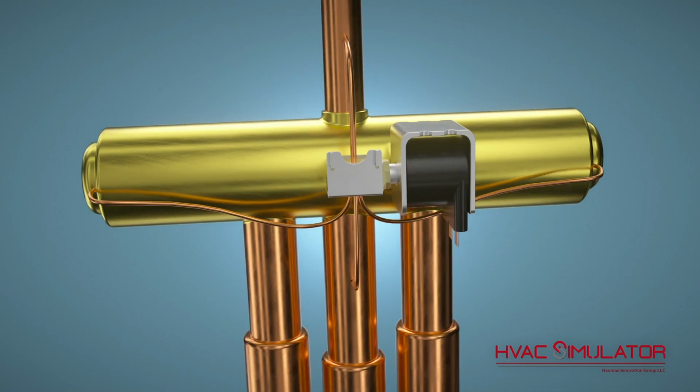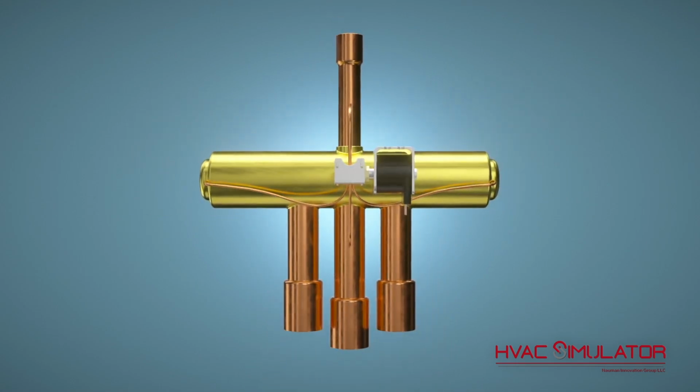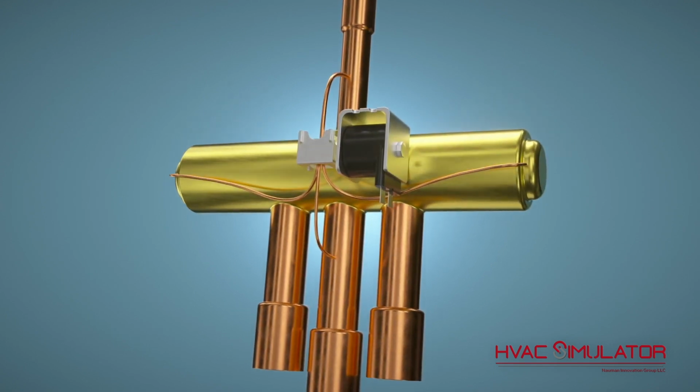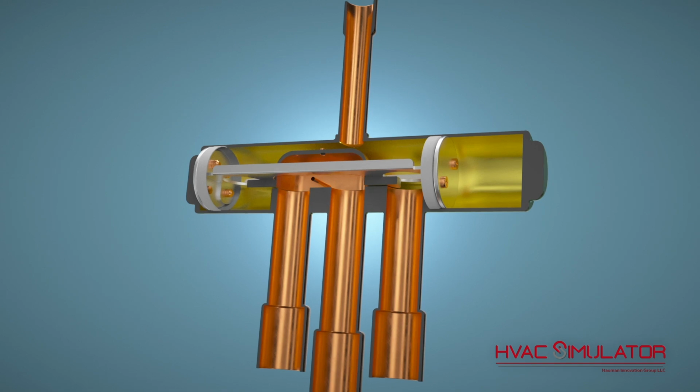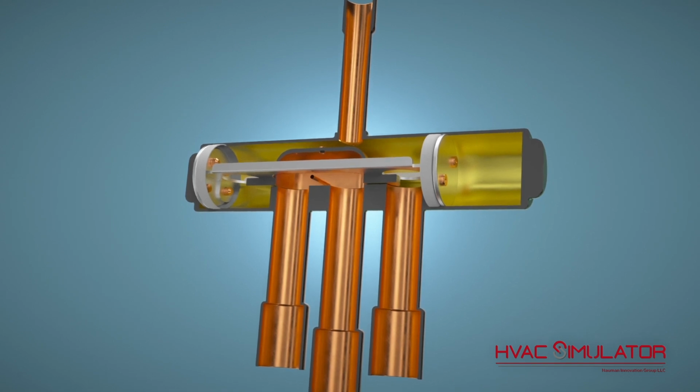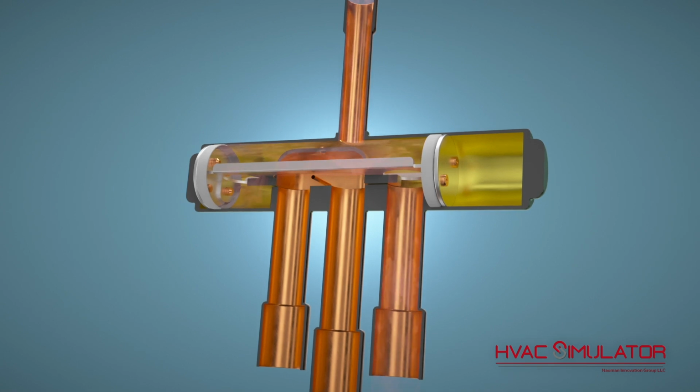The pilot valve and valve body both direct the flow of refrigerant. The pilot valve's mechanical movement is by electromagnetic force, whereas the movement in the valve body is by refrigerant pressure. Let's take a closer look. First, examine how the refrigerant flows through a reversing valve with a de-energized solenoid coil. In this example, a de-energized solenoid coil represents heating.